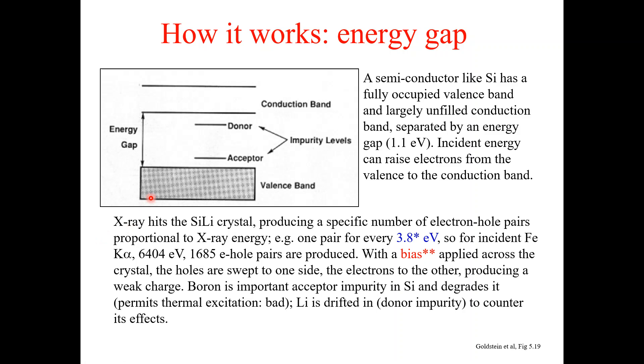When x-rays hit the silicon-lithium crystals of an EDS detector, they produce a specific number of electron-hole pairs proportional to the x-ray energy. As an example, if one electron-hole pair is generated with an energy of 3.8 electron volts, and we have an x-ray from iron with an energy equal to 6404 electron volts, then by this analogy we can generate 1685 electron-hole pairs.